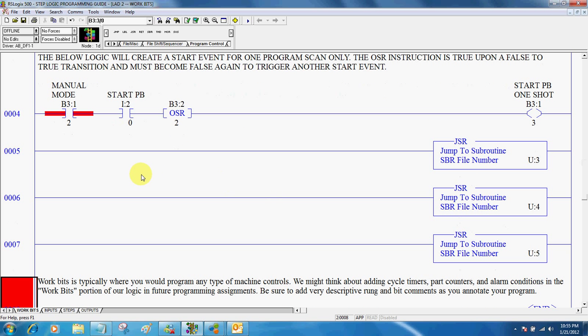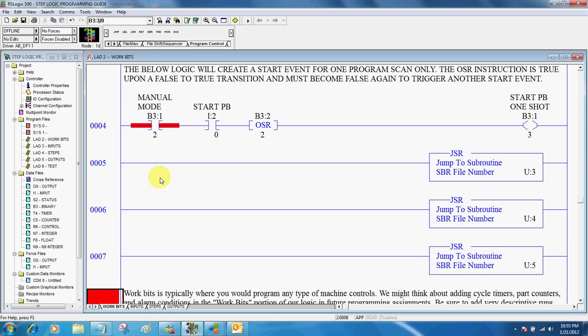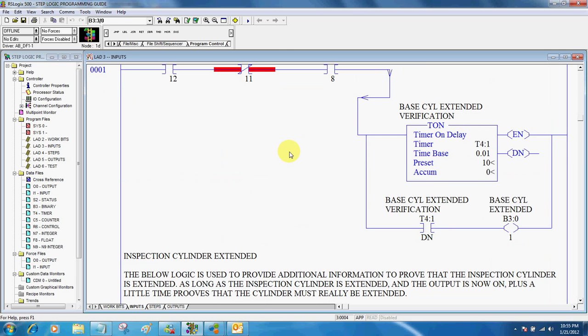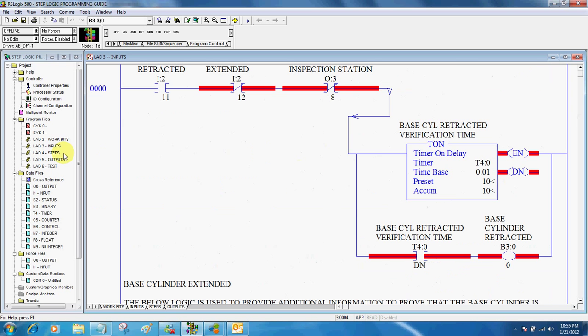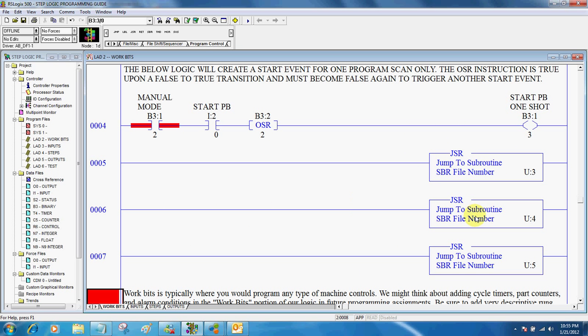And the last thing that we must put in our work bits here is some JSRs. So we want to jump to subroutine U3, U4, and U5 because this is the last line of code in this rung. So we jump to U3, and what that means is we're going to jump over here to ladder three. We're going to scan all of our inputs here. And then it's going to return back to the main program and then jump to U4, which would be our steps. Comes back, jumps to U5, and then goes to the outputs, and that completes one program scan.